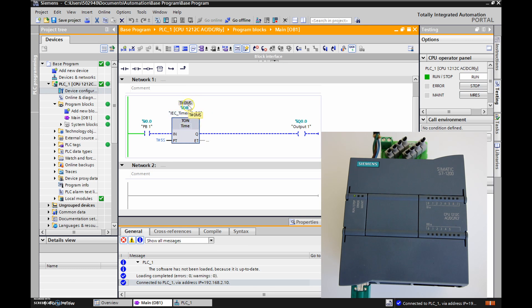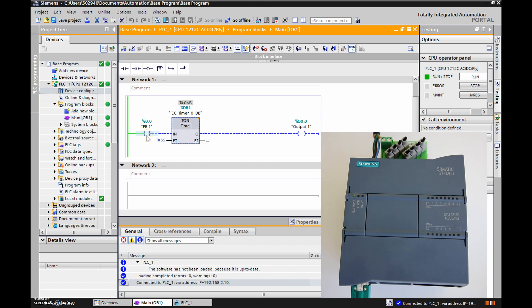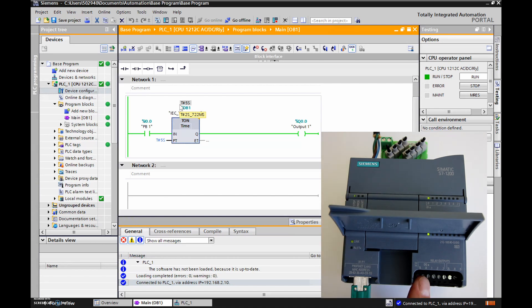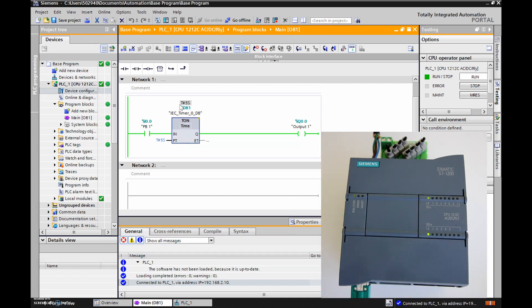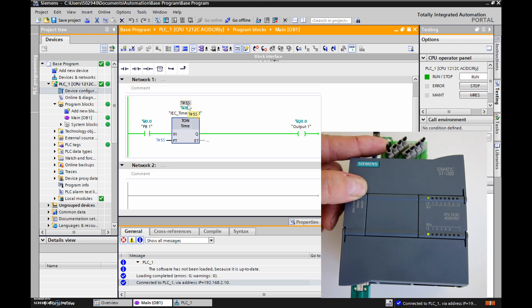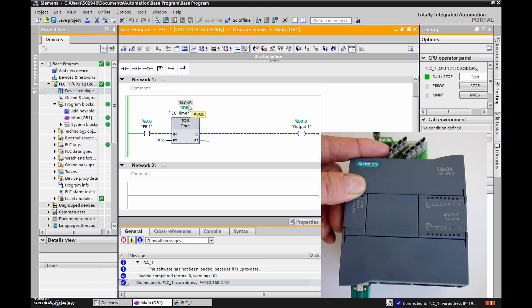Once the switch is closed it's going to increment up to five seconds, and we'll see the value changing here in milliseconds. Once it gets to five seconds the output should fire on and the Output 0 LED will illuminate. Let's close this switch and start timing — you can see it incrementing: three, four, and at five the output turns on. Now if we stop logic continuity by opening the switch, the timer turns off and goes right back down to zero milliseconds.